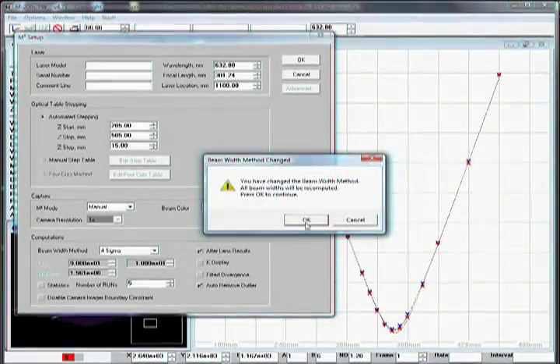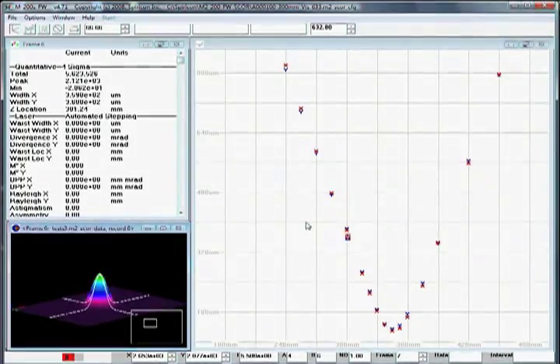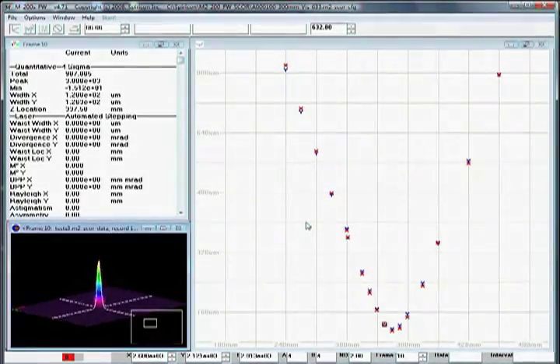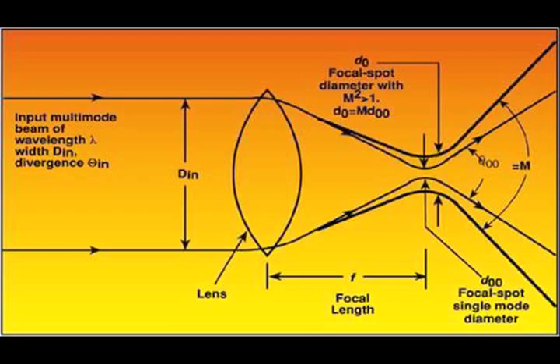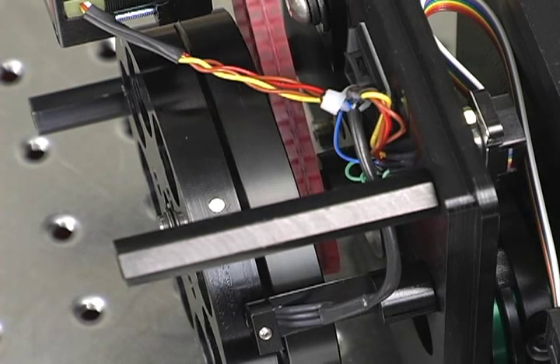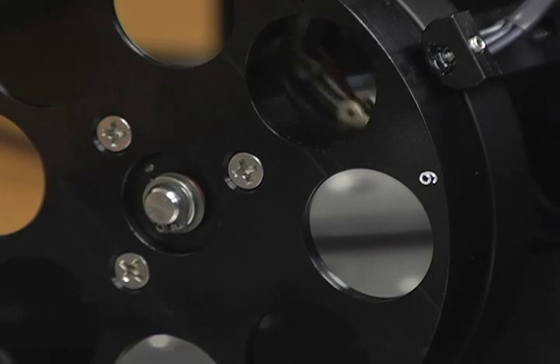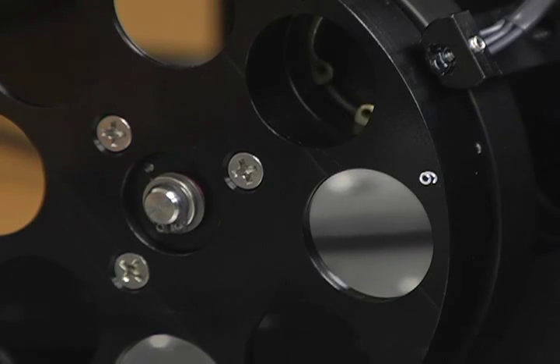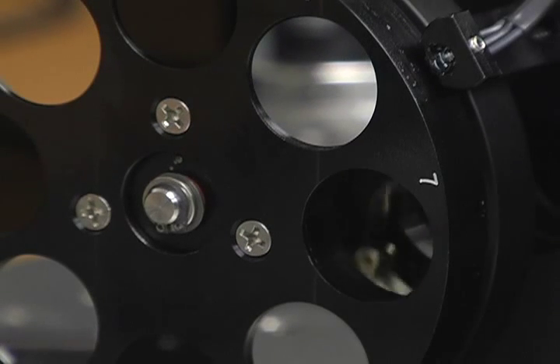The system automatically analyzes the beam by scanning the focusing caustic. When transitioning from the close far field through the focus and then into the distant far field, the intensity of the beam at the camera will change significantly. The computer software selects the proper ND filter combination so that the beam's sample intensity is optimized at each point along the caustic.